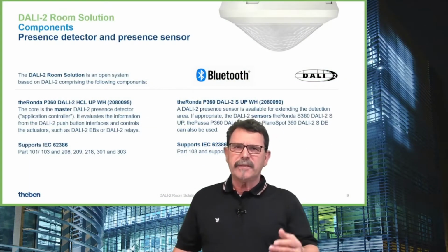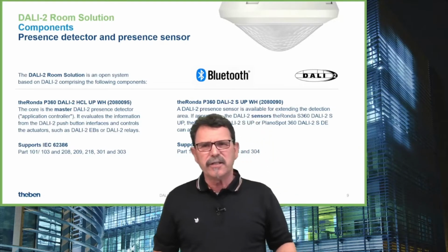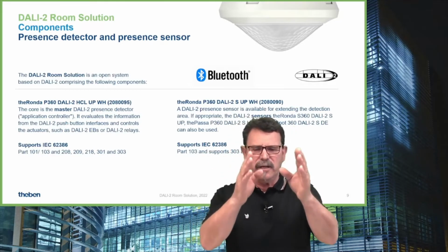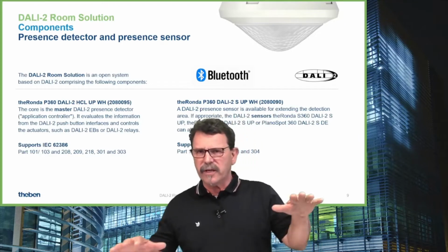By the way, this beautiful sensor here is the brand new DALI-2 HCL sensor, which is the controller, the master, however you like to name it. This sensor is good enough to give you 3 different light measurings. That means, first of all, directly underneath. Then heading to, let's assume, the inner side of the room. And this one sensor is measuring towards the window side. And so you can totally independently control 3 different light sources, finally, as you like.